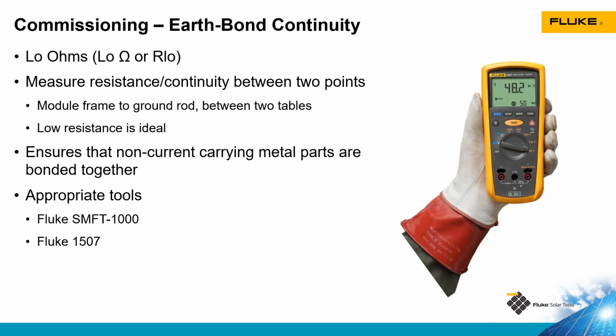There's an IEC standard for this type of test that requires a 200 milliamp test, which is a current level that is much higher than what a standard multimeter is capable of doing when doing a continuity test. They're typically operating at 50 milliamps. The SMFT 1000 and the 1507 insulation resistance tester can both conduct this earth bonding continuity test at the 200 milliamps required by that IEC standard.